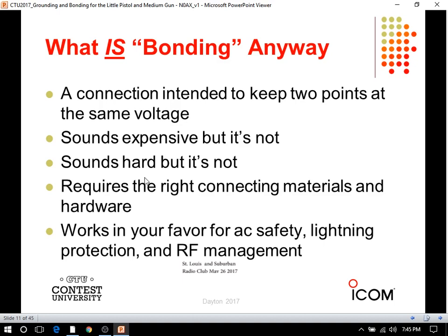You're just trying to connect it all together so that when RF comes into the station, or a lightning pulse or transient comes into your station, it sees it as one giant electrical thing that's all connected together. So it doesn't pick out one piece of equipment and say, I'm going to go there. You want it all to come up and all to go down at the same time.